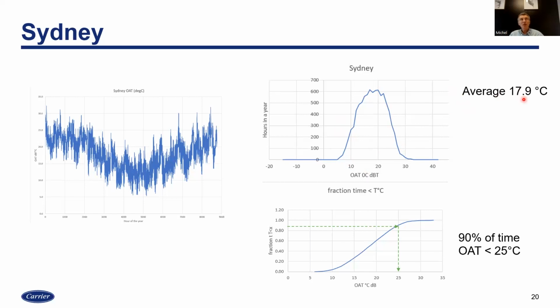So now, if your data center water temperature is 30-20, it means on average you can do a significant amount of cooling because you can go from 30 to 20. You will have enough free cooling. I also did another kind of sorting of those data. It's a kind of integration of this curve. Basically, how you read this: if you put the pointer on this curve and you look left, it will tell you how many hours temperature is below a certain level. So if you take 30 in Sydney, you will see that 100% of the time, almost, temperature is below 30, which was a surprise for me. If you take 15, about 40% of the time temperature is below 15.